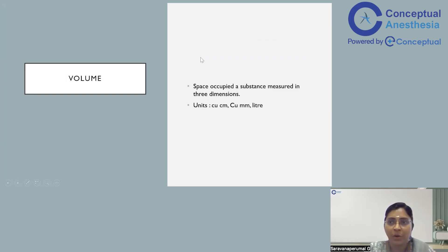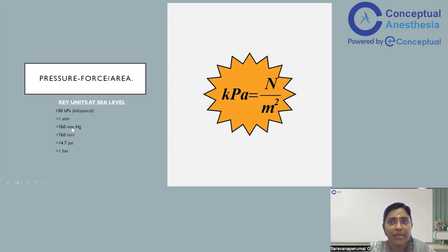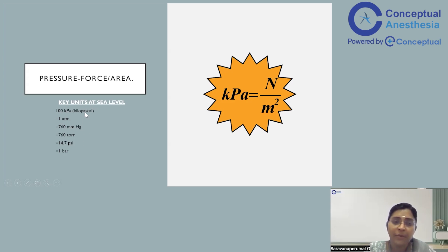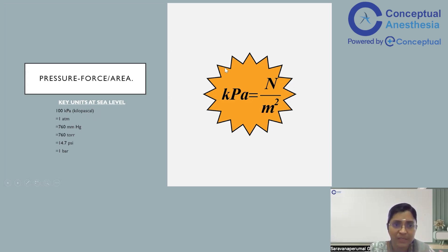Volume is the space occupied by a substance at any given point, measured in a three-dimensional manner — either as cubic millimeter, cubic meter, or as a litre. Pressure is force divided by area, so kilopascal is Newton divided by meter square. There are many units in which pressure is measured, and it is imperative to know all of these because pressure gauges may show bar or PSI. 100 kilopascals equals one atmosphere, which is 760 mmHg, or 760 Torr, or 14.7 PSI, which equals 1 bar. Our oxygen cylinder will be somewhere close to 2000 PSIG or 137 bar.